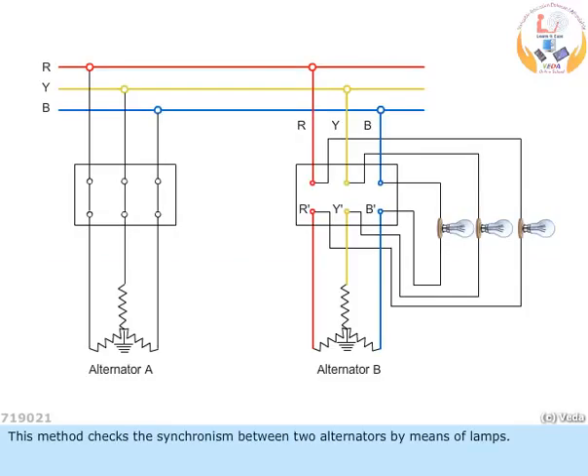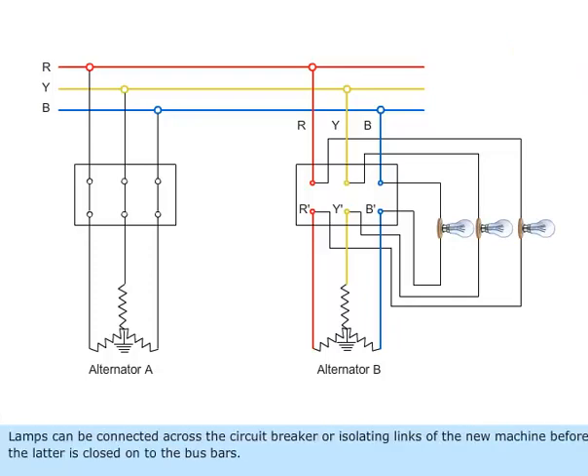This method checks the synchronism between two alternators by means of lamps. Lamps can be connected across the circuit breaker or isolating links of the new machine before the latter is closed onto the bus bars.